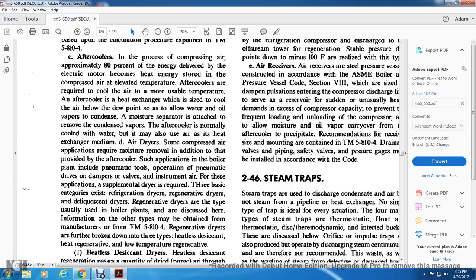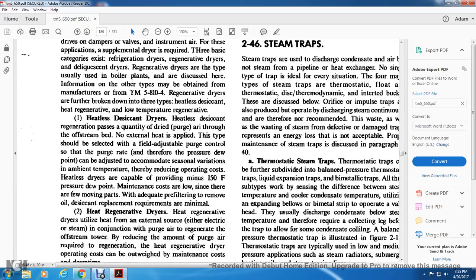Regenerative dryers are further broken down into three types: heatless desiccant, heat regenerative, and low temperature regenerative. The heatless desiccant dryer. The heatless desiccant regeneration passes a quantity of the dried purge air through the off-stream bed. No external heat is applied. The type that should be selected has a field-adjustable purge control so that the purge rate, and therefore the pressure dew point, can be adjusted to accommodate seasonal variations in ambient temperature, which reduces operating costs. Heatless dryers are capable of providing a minus 150 degrees Fahrenheit pressure dew point. Maintenance costs are low since there are only a few moving parts, and with adequate pre-filtering, the oil desiccant replacement requirements are minimal.